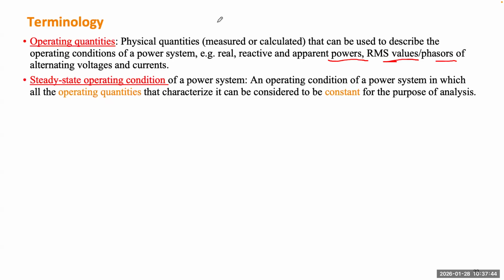Later we can add frequency if the frequency can change. The next term is the steady state operating condition. A steady state operating condition is a condition of the system in which all operating quantities that characterize the system can be considered to be constant, only for the purpose of analysis. But those quantities are not constant. If you're able to measure the voltage, power, and current, even when there's no fault, because the system has the load changing all the time, you will see the voltage and current fluctuate at very little magnitude, but stay pretty close to around the same value, around the nominal value.